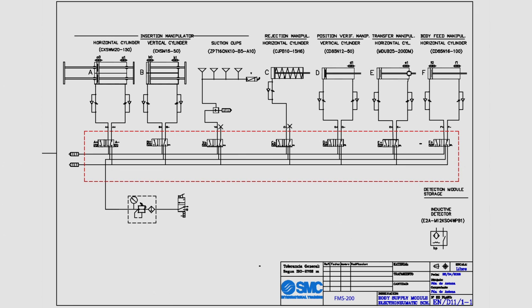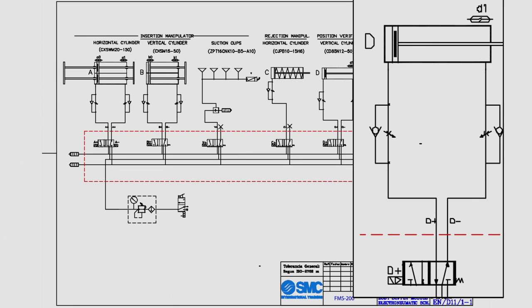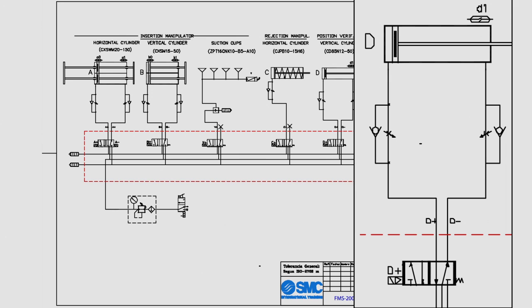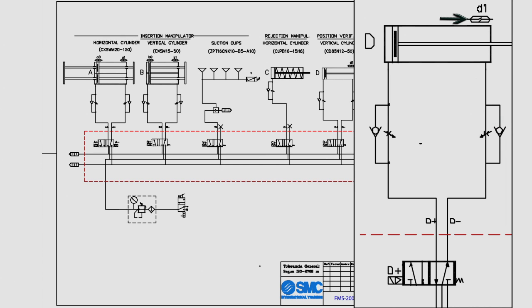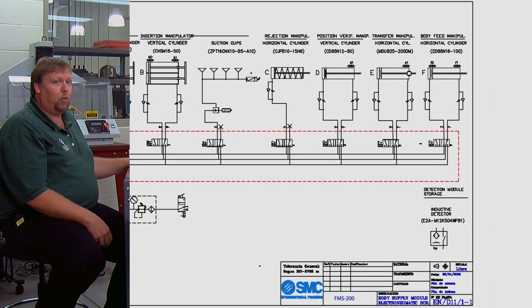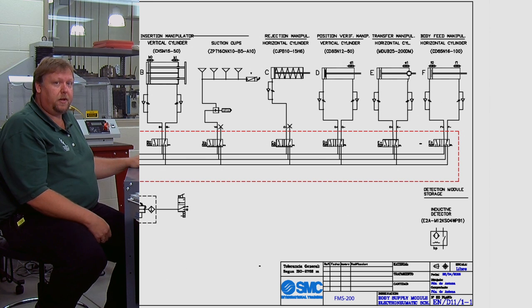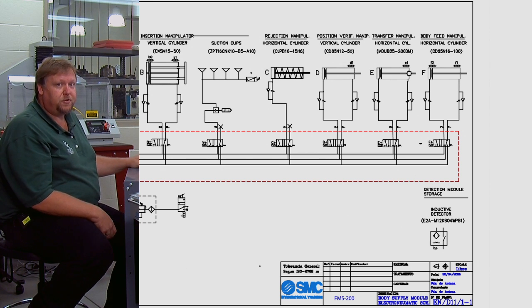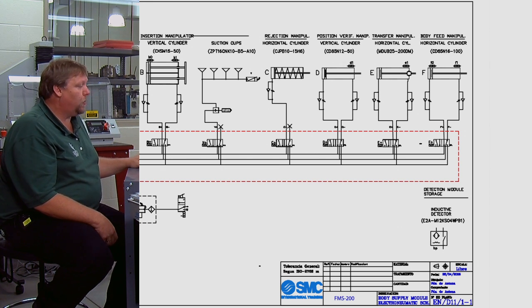Okay our next cylinder here is the position verify or they call this the vertical cylinder. Again it has the exact same type of valve. Has flow controls on both the inlet and the outlet and it also has position verification, but it only has verification on one end of the cylinder. So we will only know when this cylinder is extended and that's going to be important because we might need to provide provisions for that in our program.